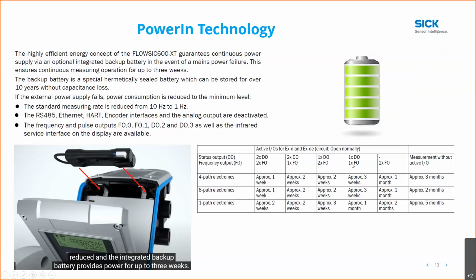And of course, as you go to the right, depending on how much I/O you're using, if you're only using your frequency outputs on a 4-path meter, you can last up to 1 month off that battery. One of the things that does occur, though, is when you switch over to run off the battery, the measuring rate reduces and your 485 Ethernet and other options are deactivated, but you always have frequency output and discrete outputs, and all your logging is still active inside the meter.